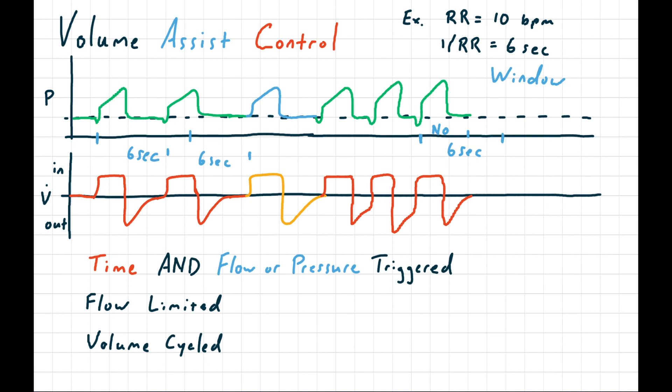That's volume assist control. Pressure assist control works exactly the same way, except that the breaths are pressure-limited breaths just like pressure control, instead of flow-limited breaths like volume control. The only difference between control, assist, and assist control modes is whether you're triggering on time, on flow or pressure, or on both. Once the breath gets started, it proceeds exactly like it would in control mode — the limit is the same, and the cycle is the same.